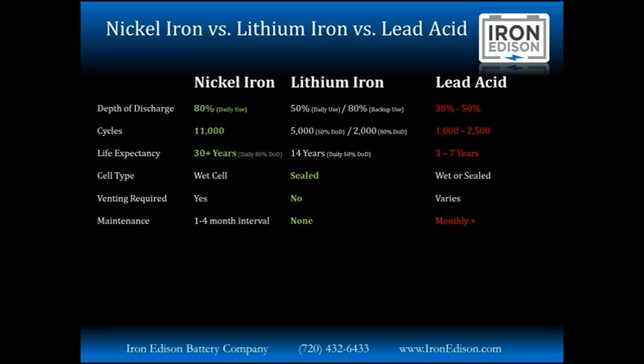Looking at the battery type, a nickel iron battery is a wet flooded cell, so it does require some venting and a little bit of maintenance, not nearly the maintenance required for flooded lead acid batteries. The only maintenance you need to worry about with a nickel iron battery, we like to have you check the electrolyte levels at least once a month. And that's very easy to do. We have a translucent jar, so instead of having to pop the cap and peer down the vent with a flashlight, you can just look at the side of the battery and see where the fluid level is in relation to the minimum and maximum fill lines. So you can check a 48-volt nickel iron battery, which consists of 40 individual batteries, in about 10 seconds.